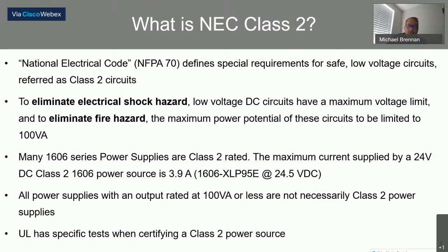So one of the things that we've seen customers struggle to understand is NEC Class 2. There are products that exist out there today that you're probably using that state on them that they require a Class 2 circuit. Now, the NFPA set special requirements for low voltage circuits, which are required to be Class 2 circuits. What that allows you to do is eliminate electrical shock and the fire hazard associated with it. But it limits the overall voltage that's available as well as the amount of current that's available. So you'll see Class 2 power supplies are limited to 100 VA.